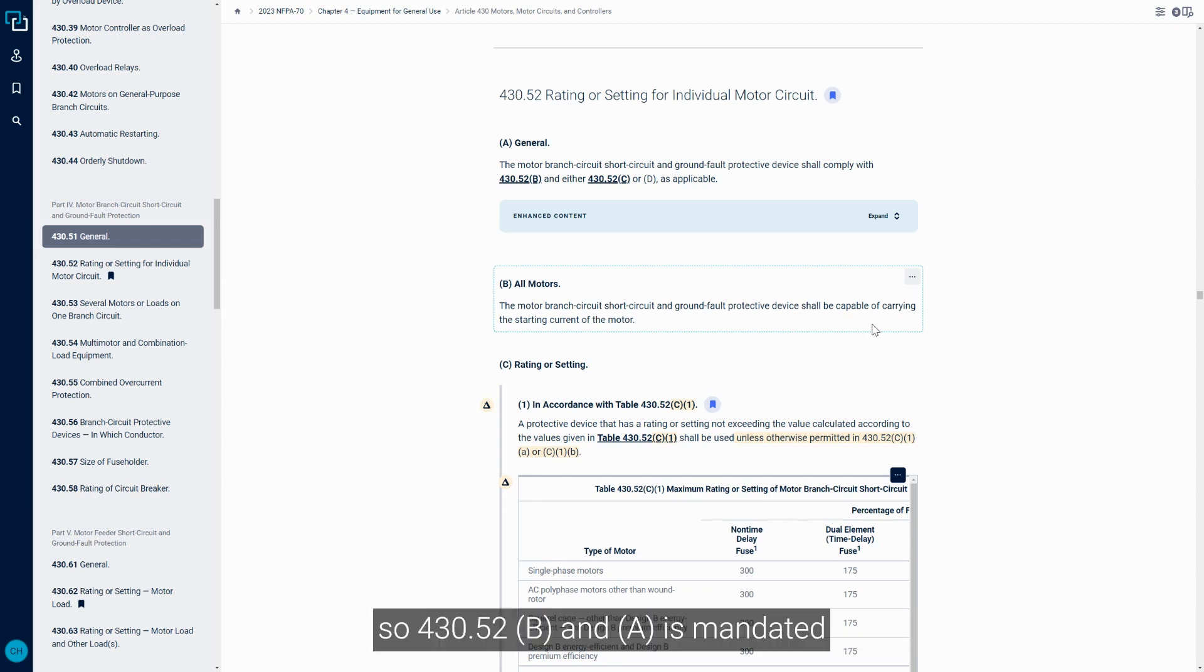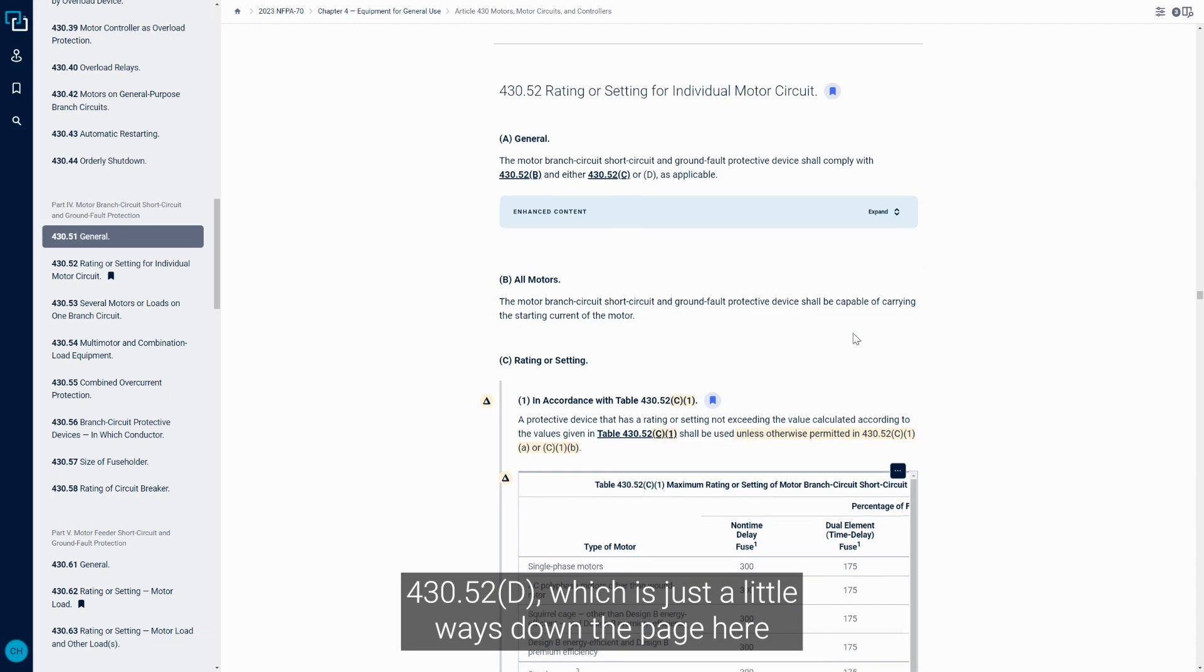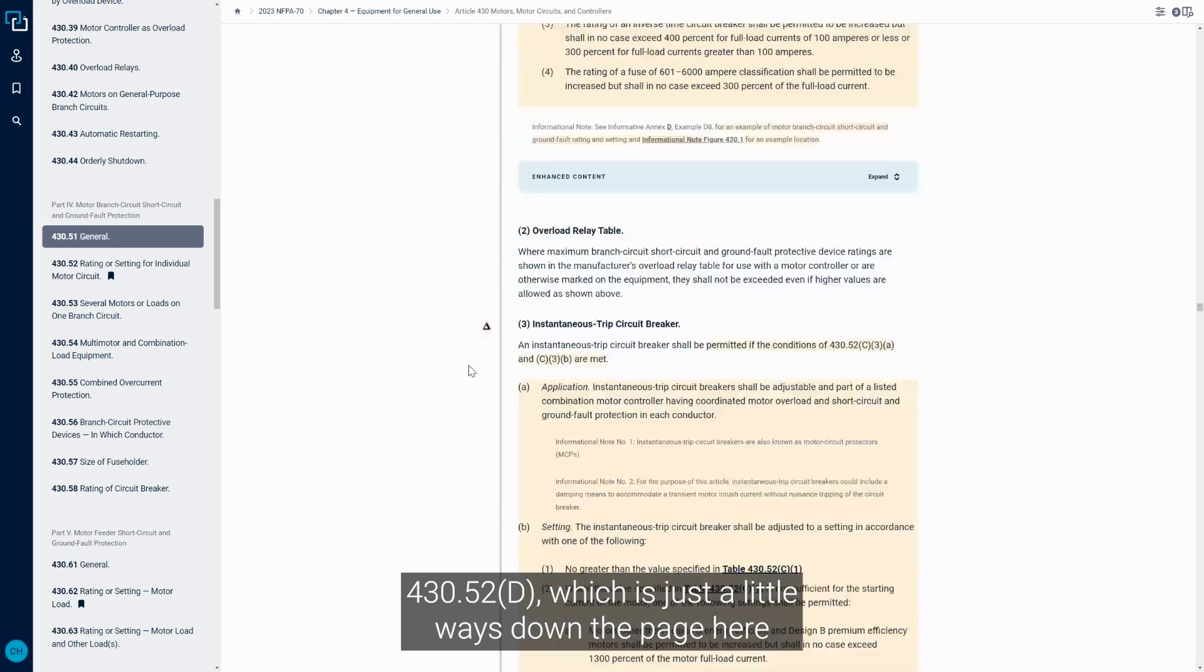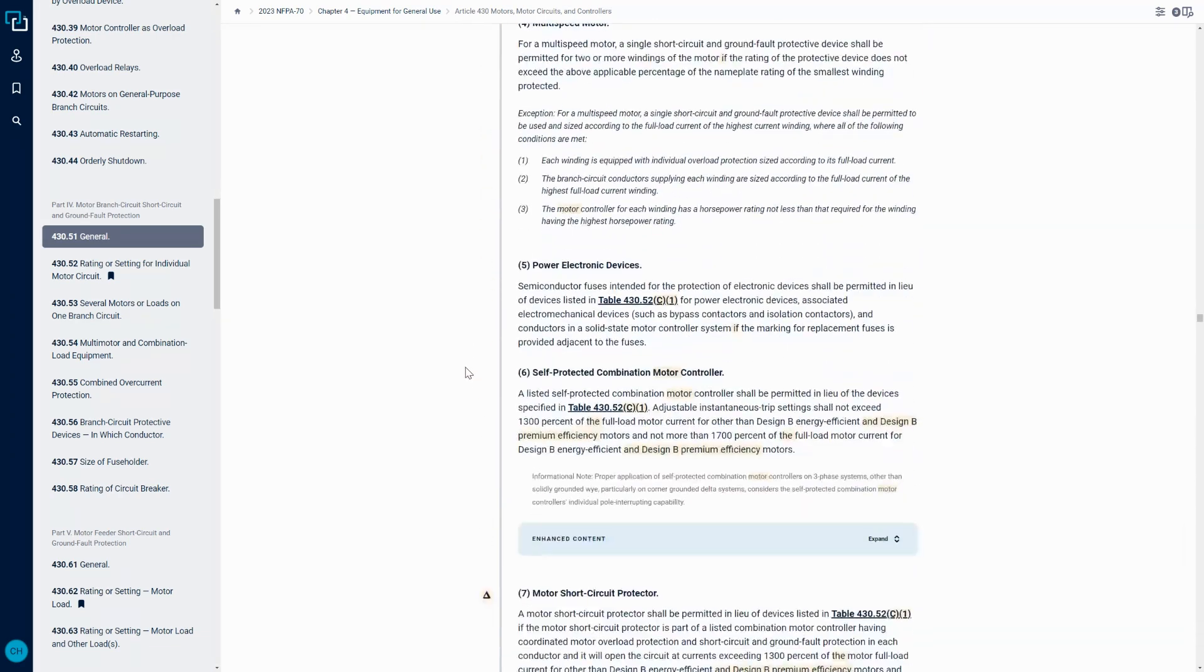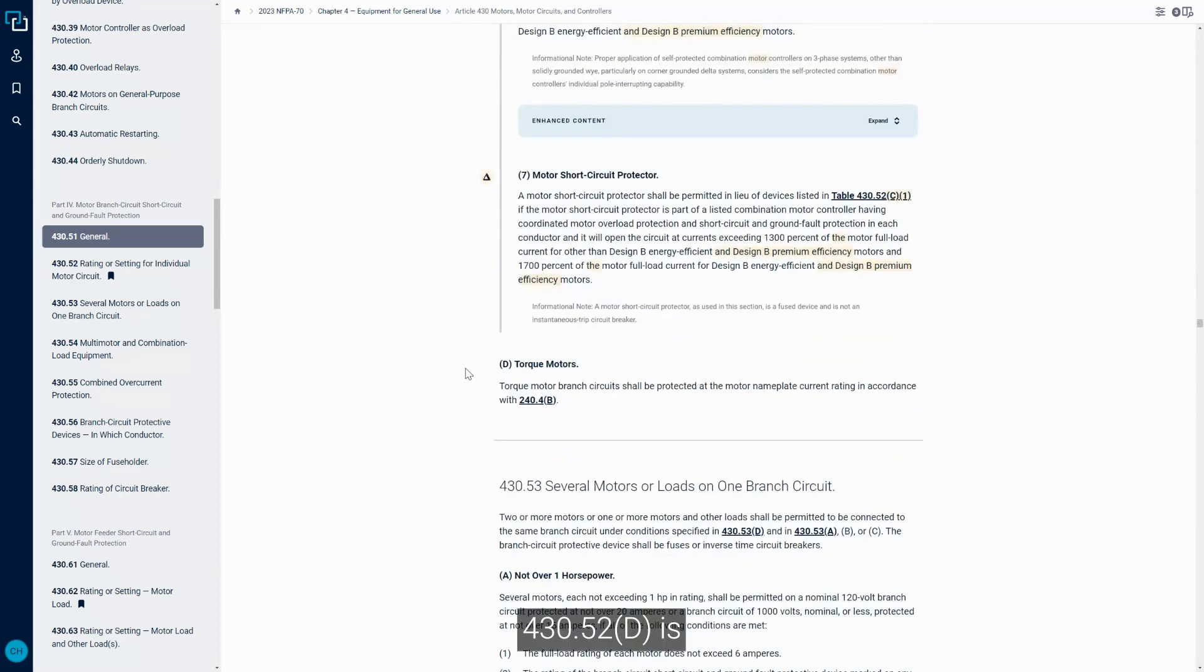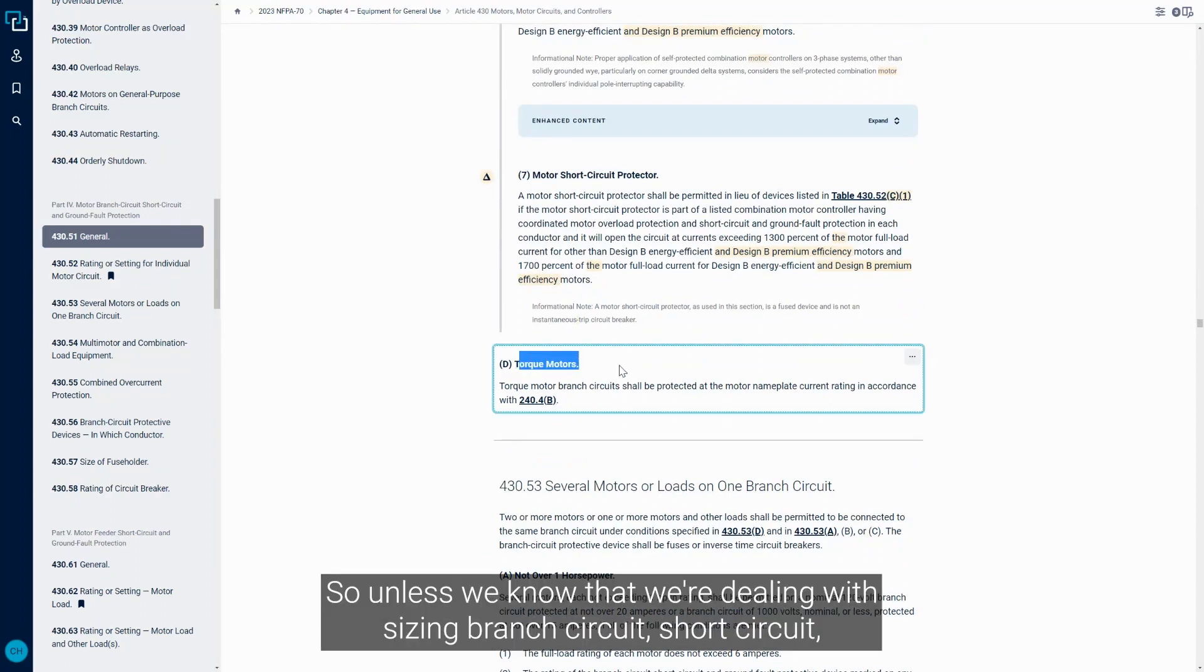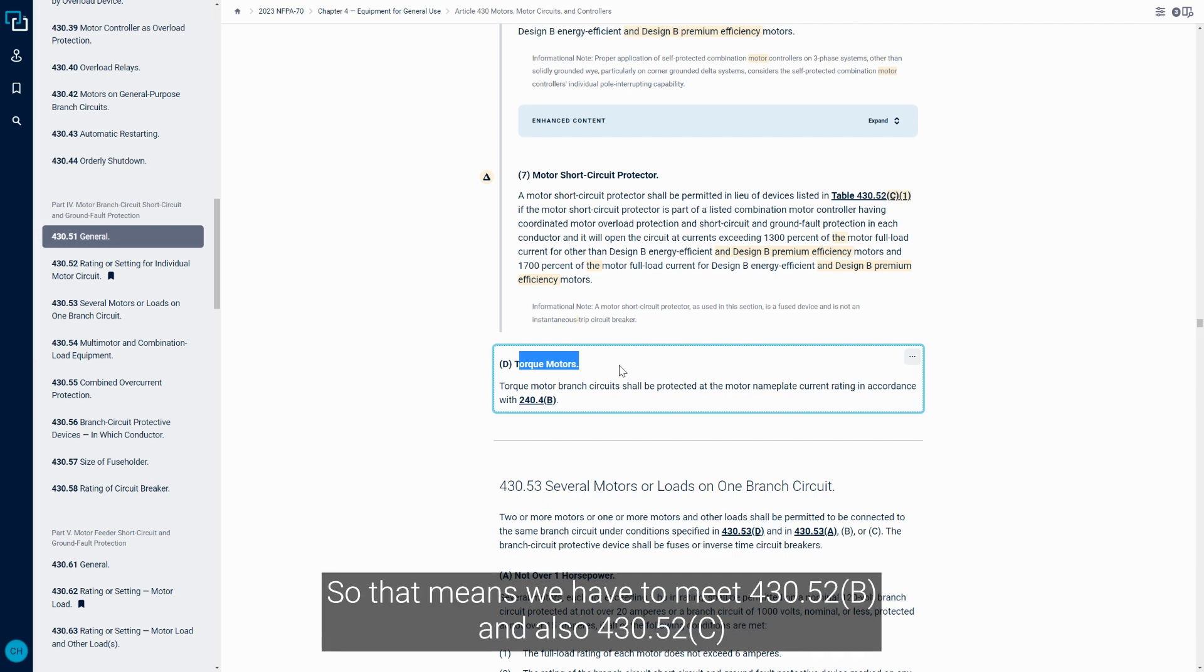So 430.52B and A are mandated, and then it's either C or D. If we move to 430.52D, which is just a little ways down the page, it deals specifically with torque motors. Unless we know we're dealing with torque motors, D is out of the equation. That means we have to meet 430.52B and also 430.52C.